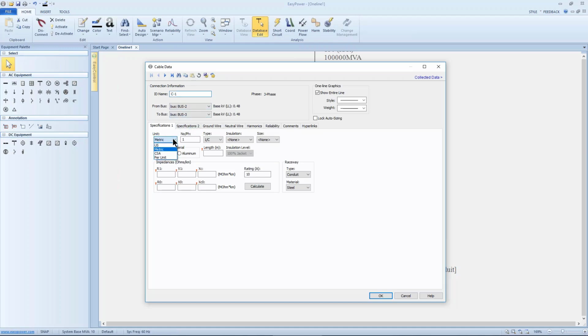So he said this first cable is US based, number of conductors per phase is 1, the type of cable is a 1C, the insulation is THWN, and the size was 350 kcmil. So we've selected there. What we've just described is a copper conductor routed through a steel conduit. He said this is 50 foot long. So we're typing in 50.